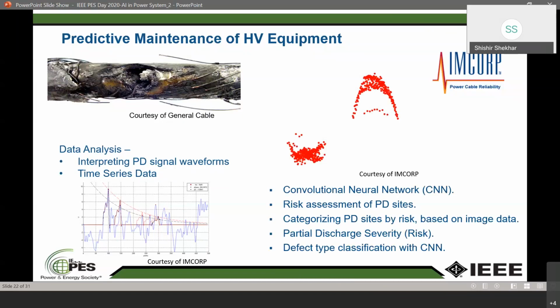So here is an example. We worked with a company called IMCorp in the US to identify faults on underground cables. What you see in the picture is a cable which has been blown due to a fault, so it's totally destroyed. When you have data from a large number of cables, you can use machine learning to look at signal patterns. There's something called partial discharge. Partial discharge takes place when you have a fault in your insulation. This insulation could be in your underground cables, in your transformers, or in other equipment. By looking at partial discharge and insulation, you can predict if insulation might fail. And if the insulation fails, you basically have a failure of the equipment.